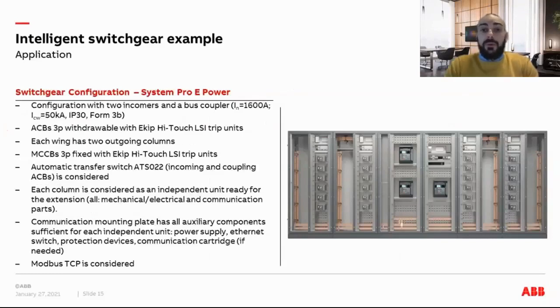First of all, we used our System Pro ePower to perform all the solutions that you will find in this detailed package documentation. We have actually two incomers and a bus coupler with 1600 amps, 50 kiloamps of breaking capacity. The IP is 30, with the segregation of a 3B form.